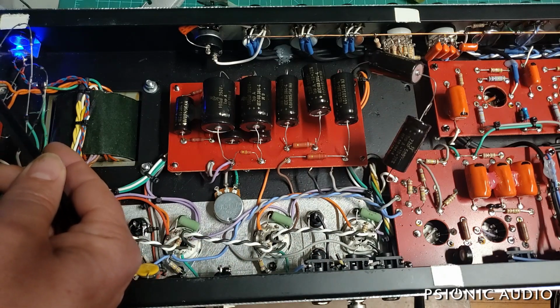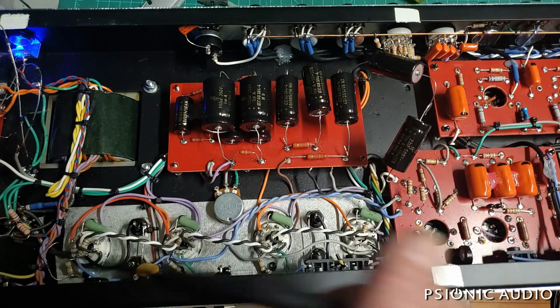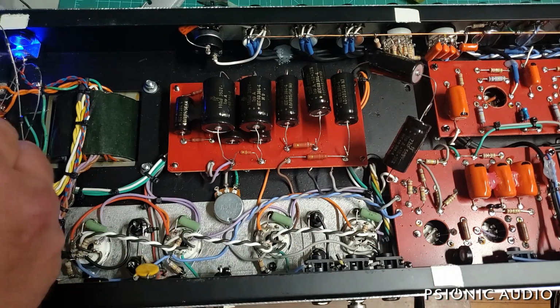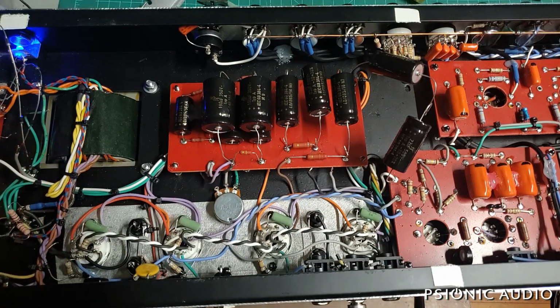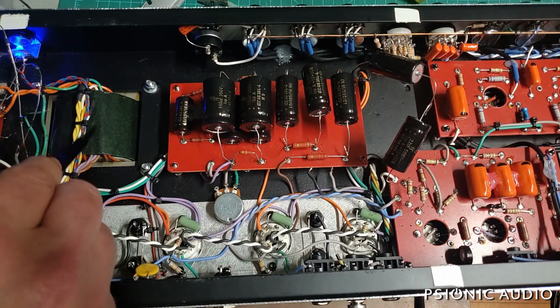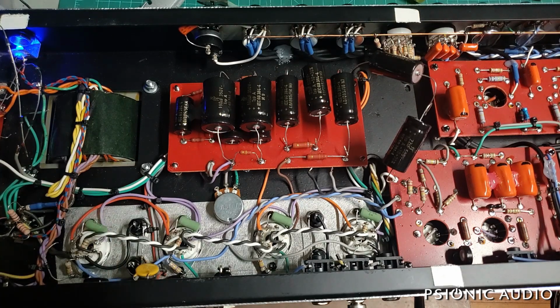As that voltage drops, the raw voltage on the HT supply, which goes to the bias — that's actually that wire going to here — goes way the hell up. And that's where we're at. So I strongly suspect it's the power transformer.